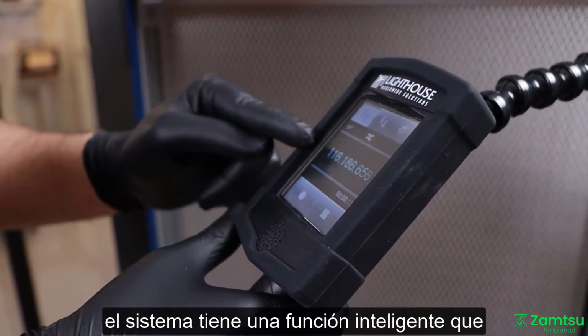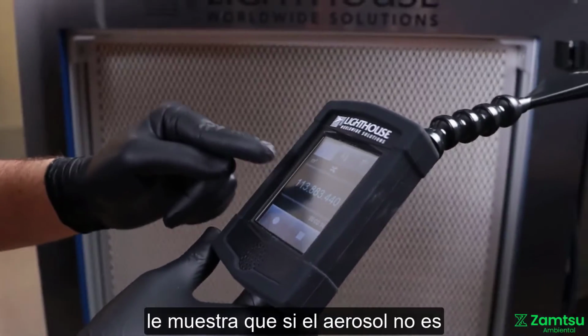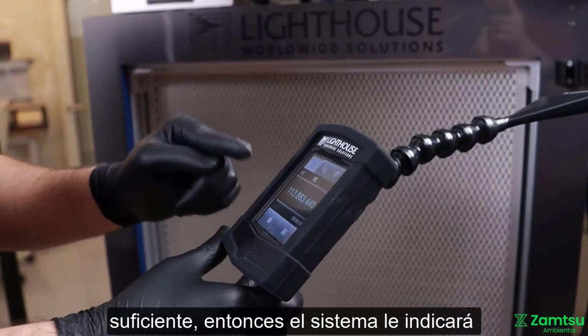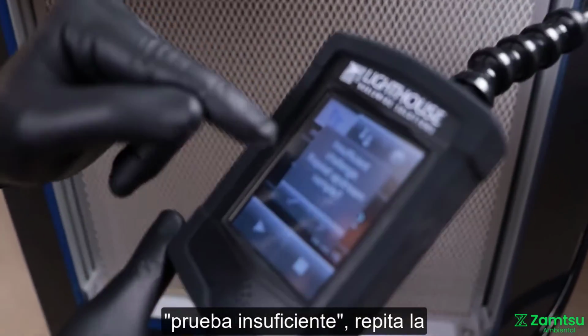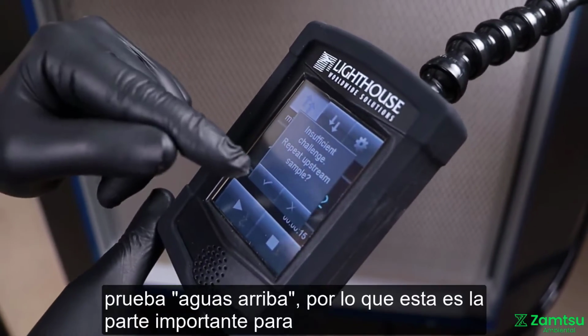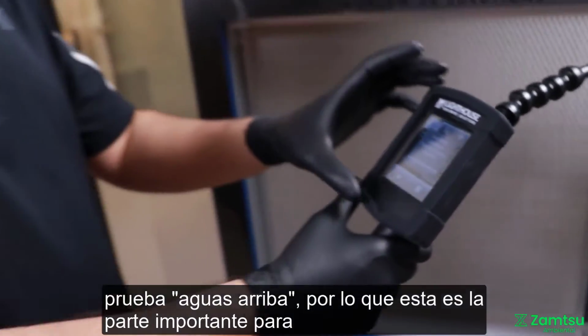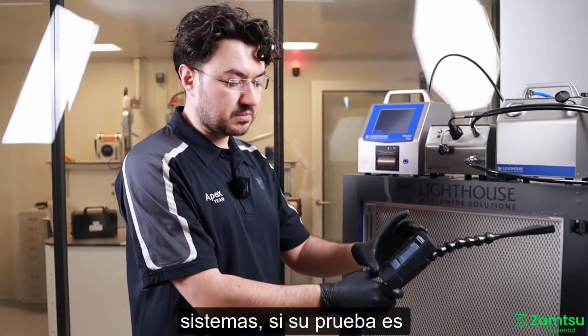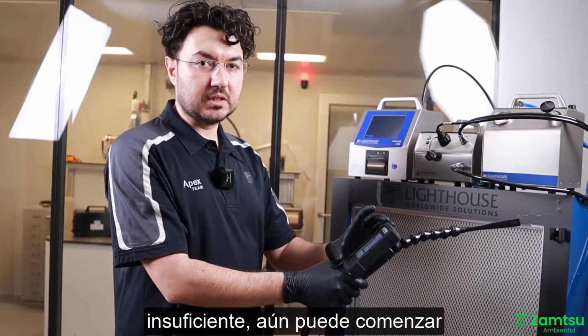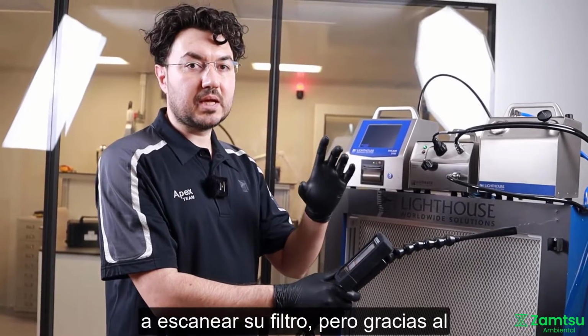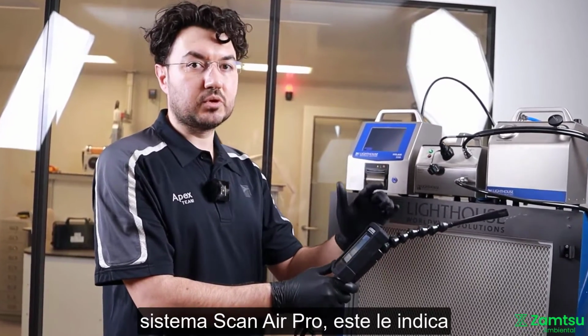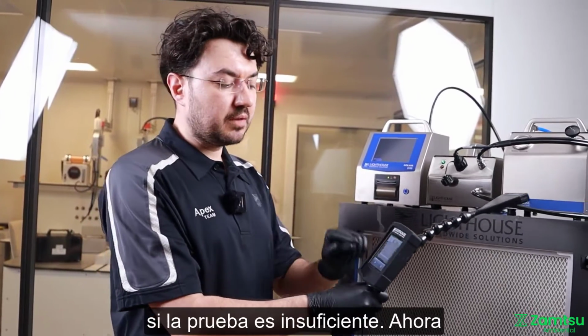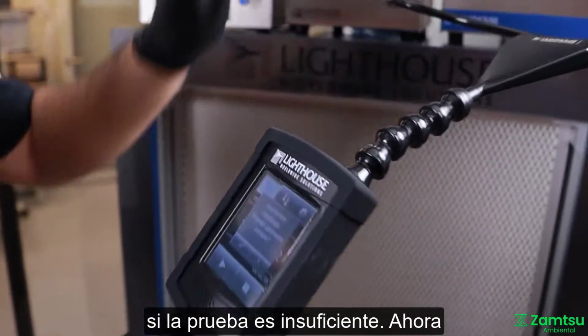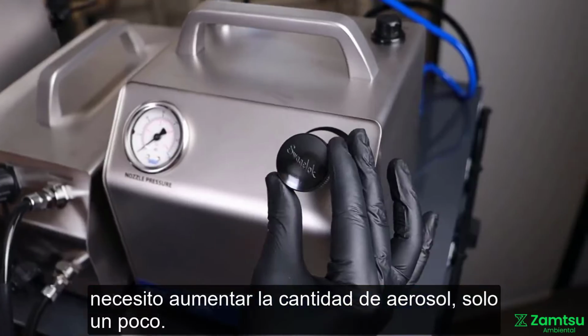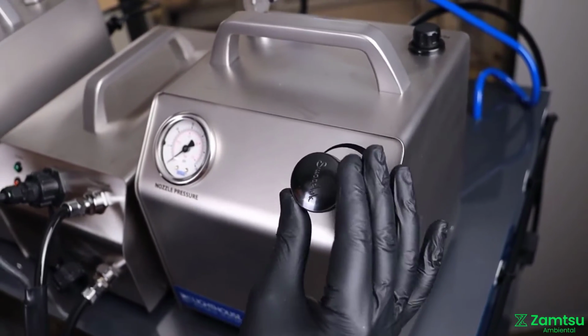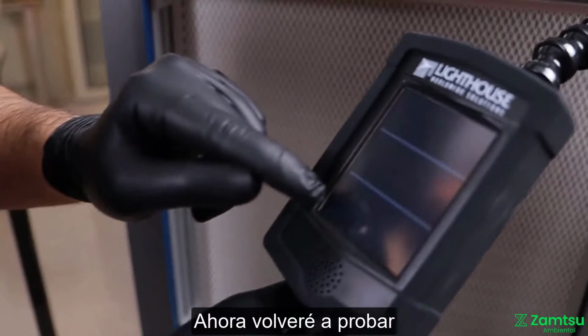The system has a smart feature which shows you that if the aerosol is not enough, then the system tells you insufficient challenge, repeat upstream sample. So this is the important part for filter testing, because most of the systems, if your challenge is insufficient, you may still start scanning your filter. But thanks to ScanAir Pro system, this gives you the feedback of insufficient challenge. Now I need to increase my challenge a little bit. I will retest it.